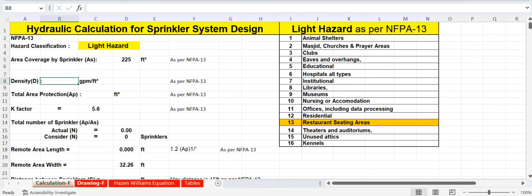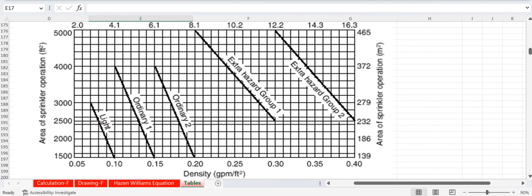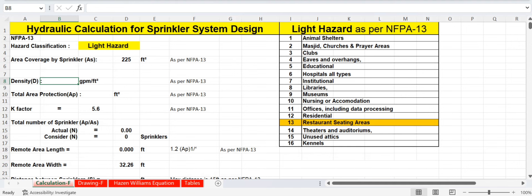For density, we refer to the density and area of sprinkler operation table. For light hazard, the required density is 0.1 gpm per square foot as per NFPA 13. Enter 0.1 gpm per square foot.